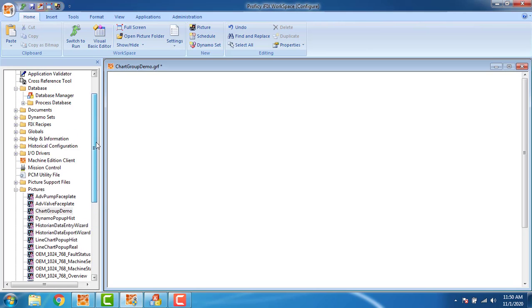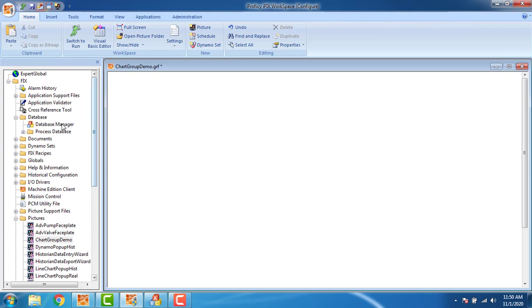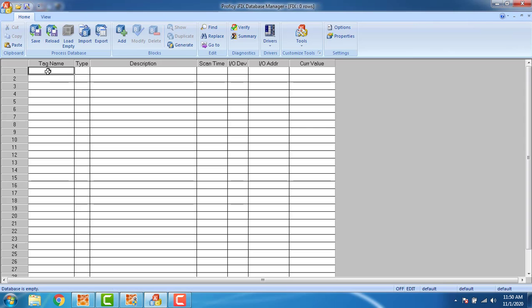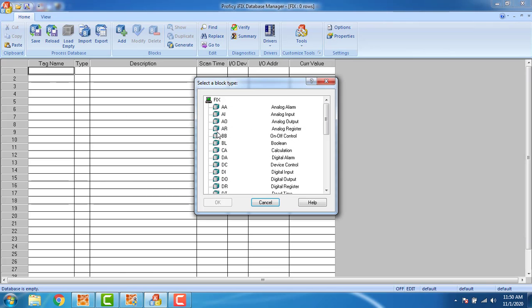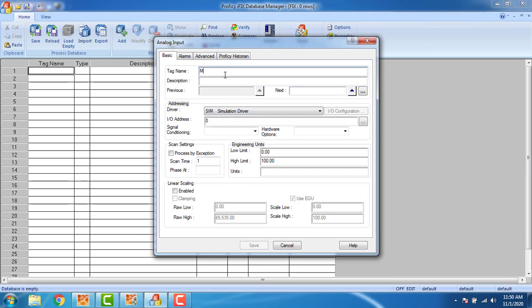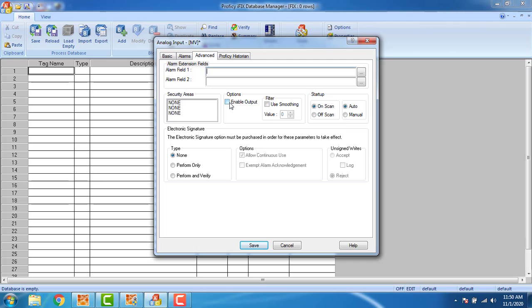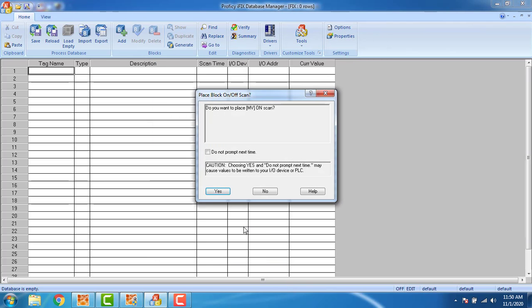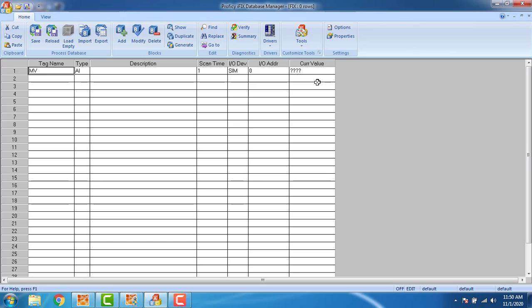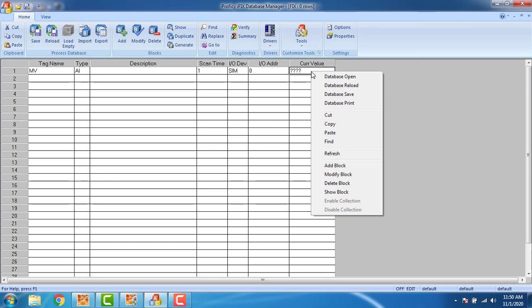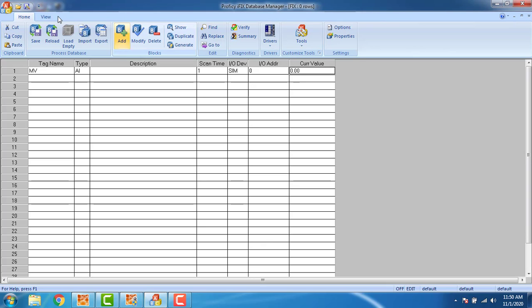Today we are going to learn about movement and visibility in iFIX SCADA. Go to database manager and create a new tag for the analog input. The type will be 'AI', the tag name will be 'MV' which represents movement and visibility. The IO address will be 0. Go to advanced, enable the output. The tag is created. Right-click and refresh — the current value is 0.0. Save and close the database manager.